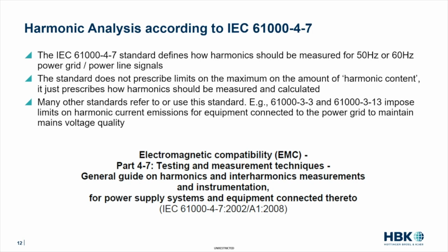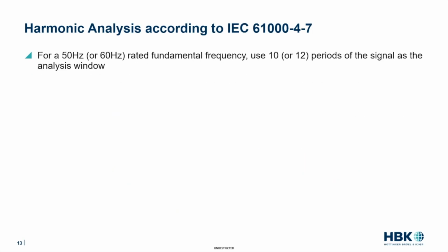And then what does the standard say about how you should measure harmonics? Well, there are several components to that, and I will not go through all of them in detail, but I will mention a few. So the first thing that the standard prescribes is that in order to determine the harmonics, you should always take a time signal that contains 10, in case of 50 Hertz signals, or 12 periods of the power grid signal as your analysis window. So what it looks like is the following.